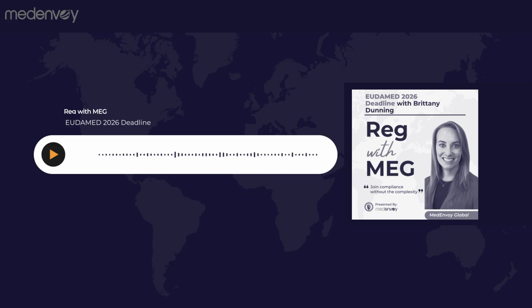Yes. So I'd say that one piece of advice is going to be three-part. The biggest thing is make one shared EUDAMED readiness map. And that can cover these three things. Number one, actor registration workflow and timing. This includes the authorized rep review and the competent authority approval cycles. The second piece is device data ownership and validation. So, who owns the basic UDI/DI, the EMDN, characteristics, member state marketing fields, and change control. And then the third piece includes downstream dependency dates for notified body certificate uploads and importer release to market verification.